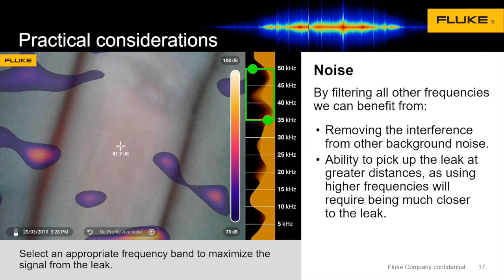Here's an image capture where you've got a bunch of different areas on the screen where colors are popping up. What I want to communicate is that we're not seeing the targets that we have seen in other examples where there's actually been leaks. You are going to get noise on the image regardless of what environment you're in. You want to make sure you can distinguish between these blobs without the full color palette and the actual circular targets, which are going to be representative of the leaks.